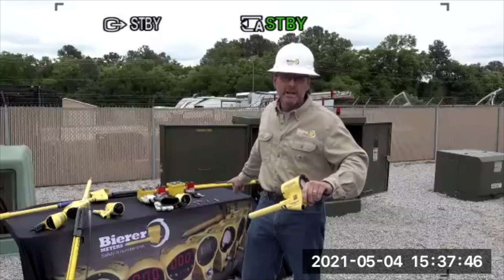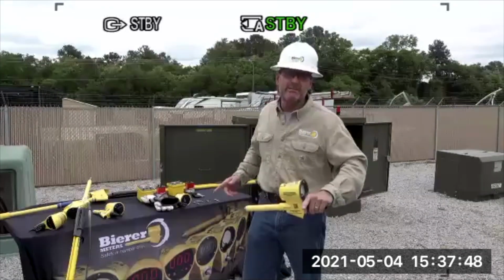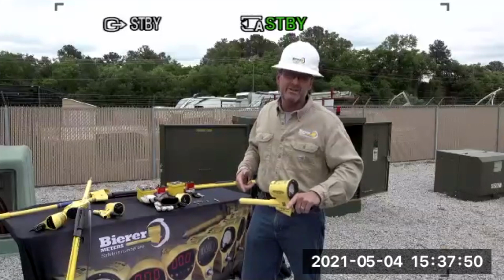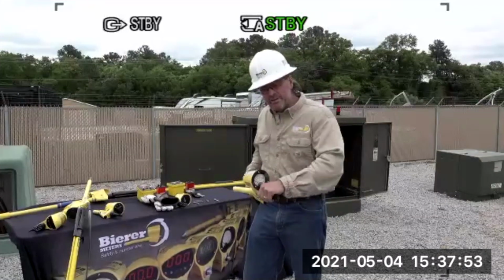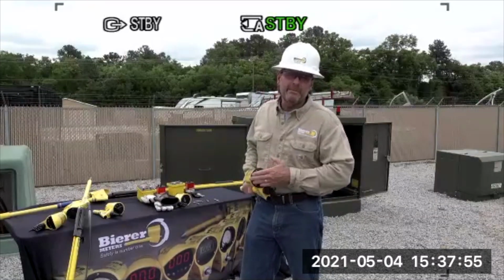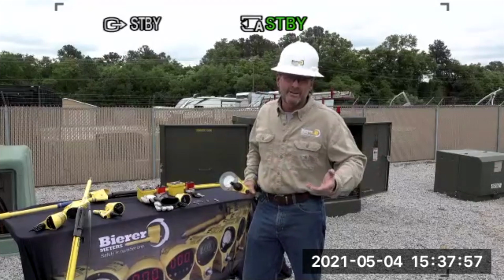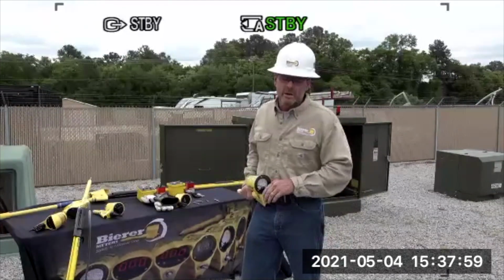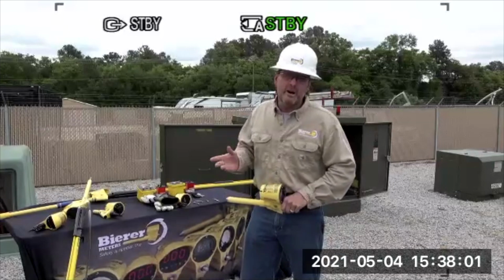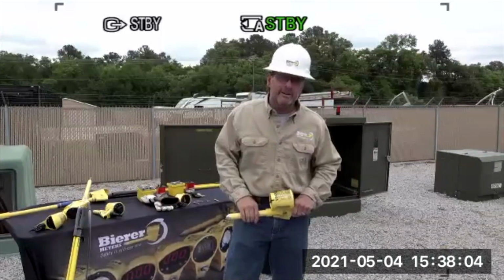From a hot bushing, we're getting about 69,000 volts on their non-contact tool. We make direct contact, and we're getting about 20,000 volts on that 19.9. So the numbers on a non-contact tool are not very accurate at all.